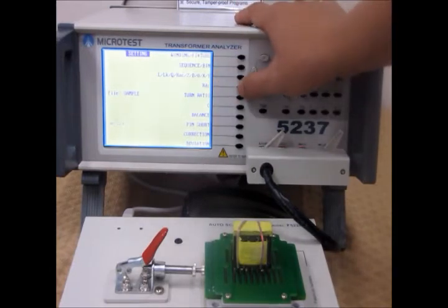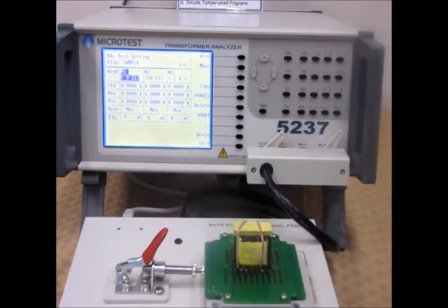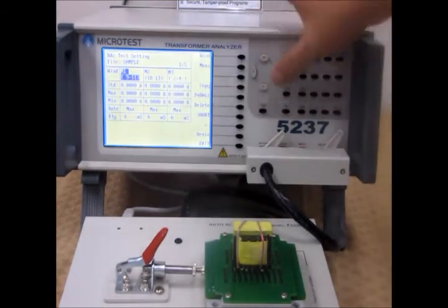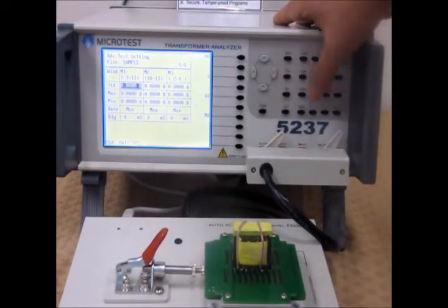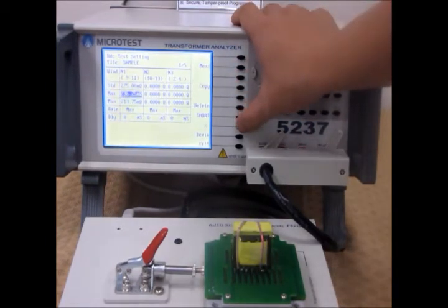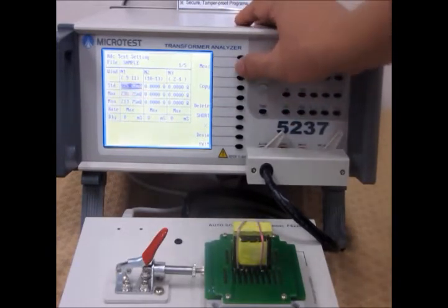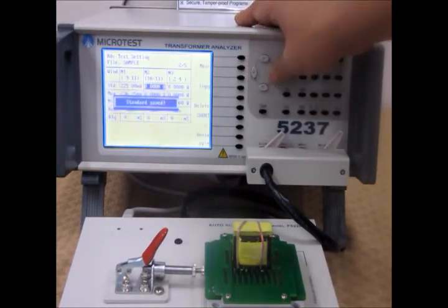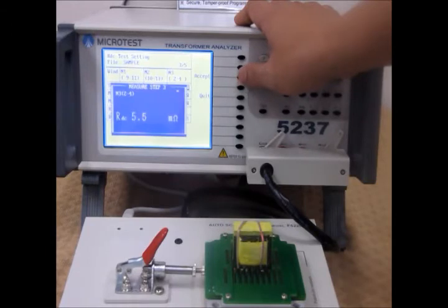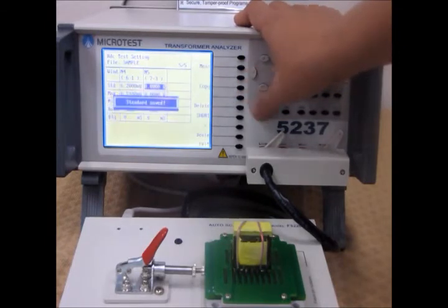You can also test the RDC. As again, you generate all the values you entered earlier. And you can set the standard value. And the tolerance. Then you can measure again. Do that for each different.